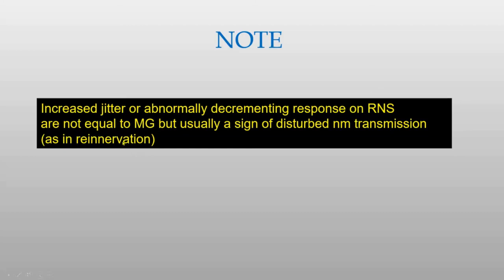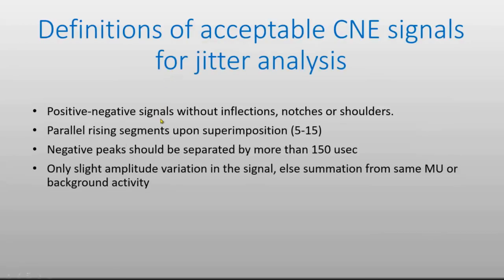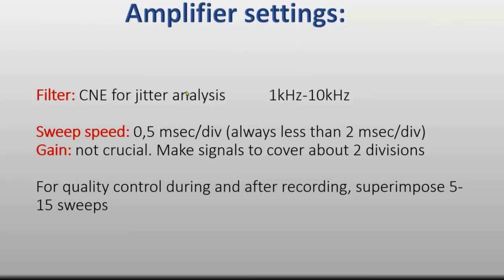Here is a summary of signals to be accepted: they should have a positive-negative inflection without notches or shoulders, meaning a parallel rising segment. The negative peaks should be separated for accurate measurements, and a slight amplitude variation is acceptable. The amplifier filter setting is 1 kHz to 10 kHz. A sweep speed of 0.5 milliseconds per division is good for detecting small changes, and the gain should make the signal cover about two divisions on screen. Superimpose 5 to 15 sweeps.